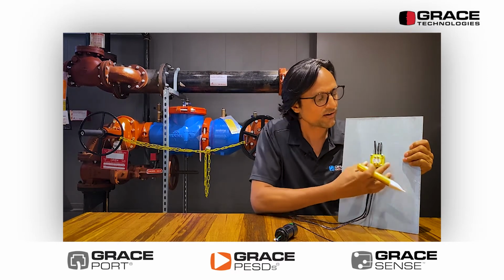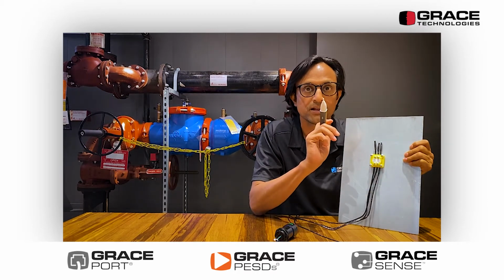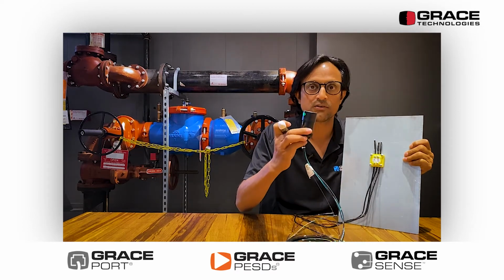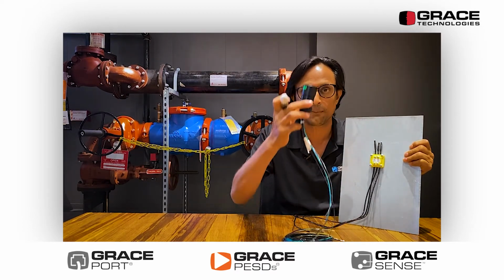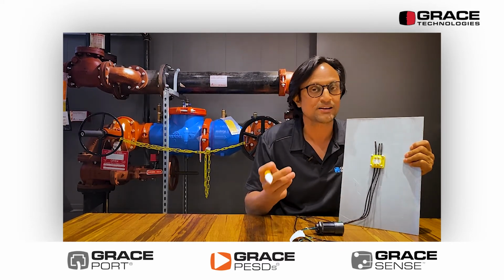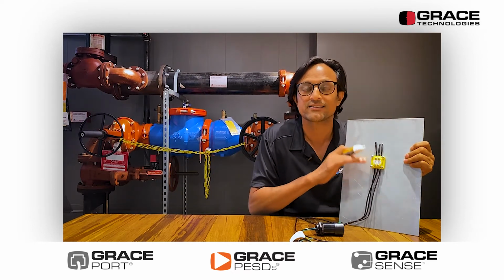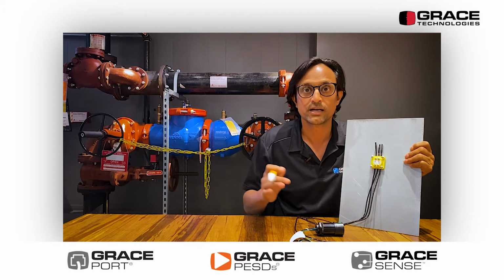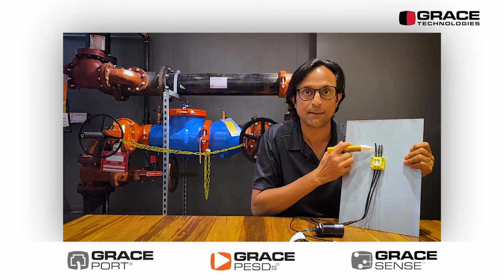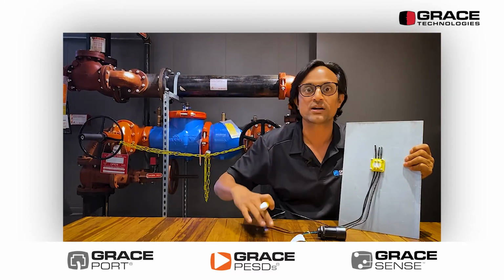One is if you're trying to use this R-3K for voltage verification using an NCVD pen and you want a redundant connection. So if you're using it with the voltage indicator, there are instances you will pass these lead wires through this device. That's one way to do it. The other way is some customers would require, I would like to have a separate set of wires so the indication is redundant and the connections are also independent. In that case, you can run your separate set of wires using this heat shrink cap kits so that you are directly connecting it to the same side of the source where your voltage indicator is connected.